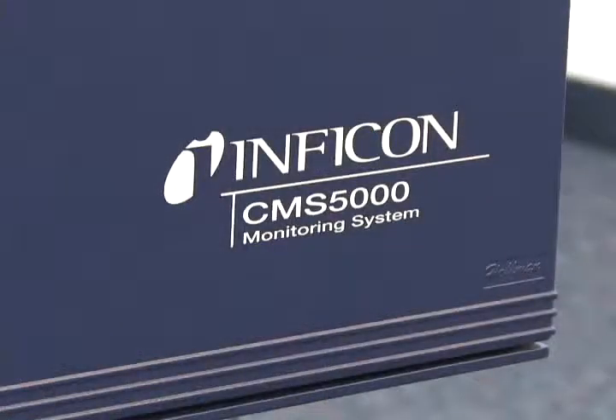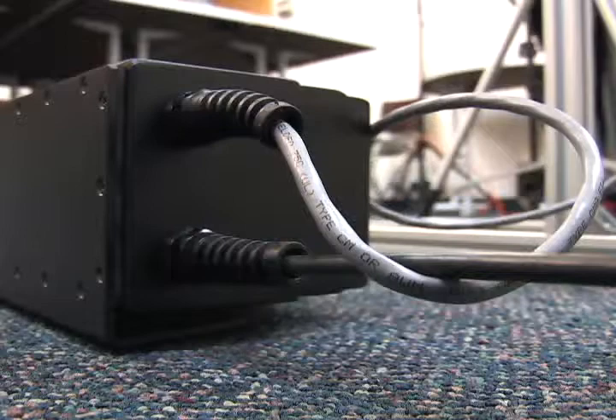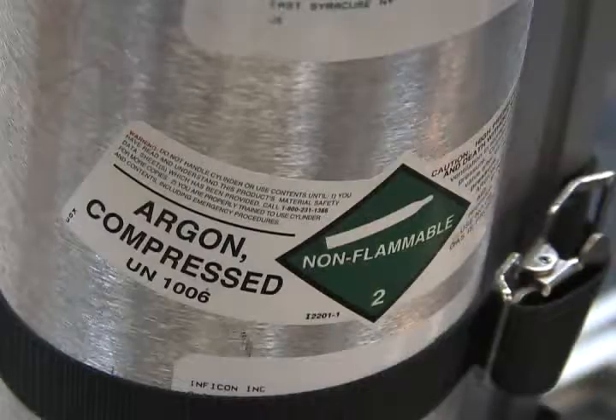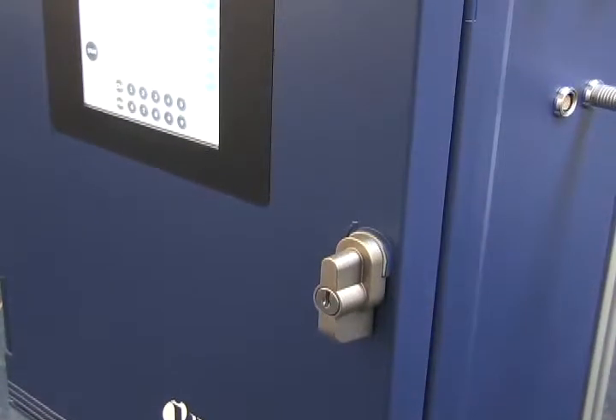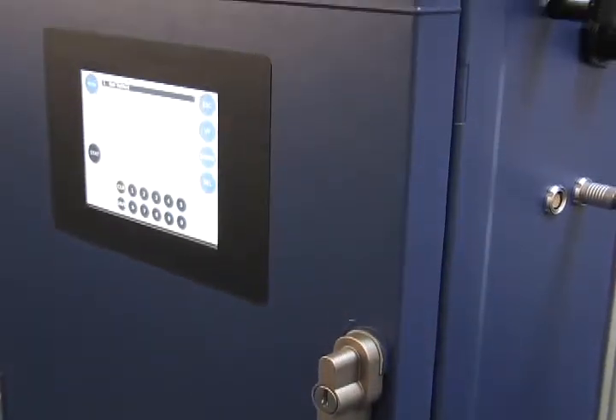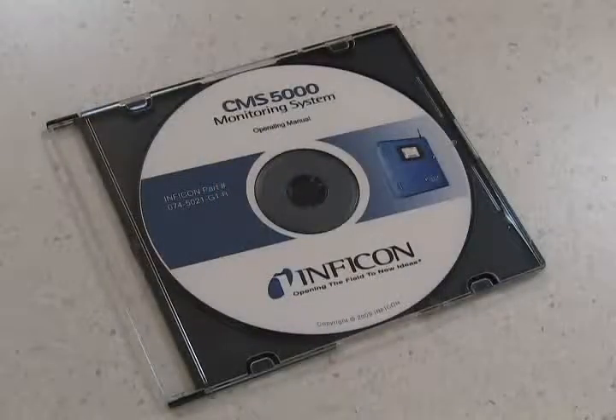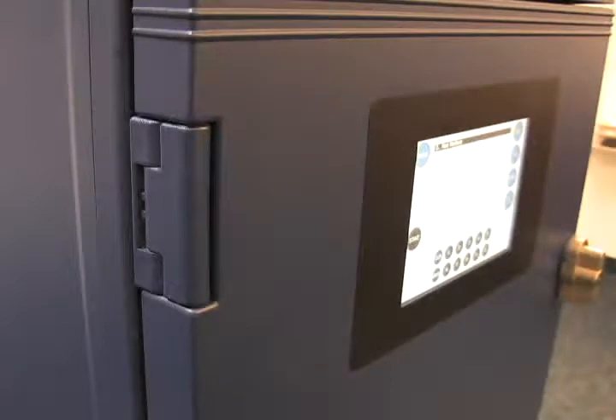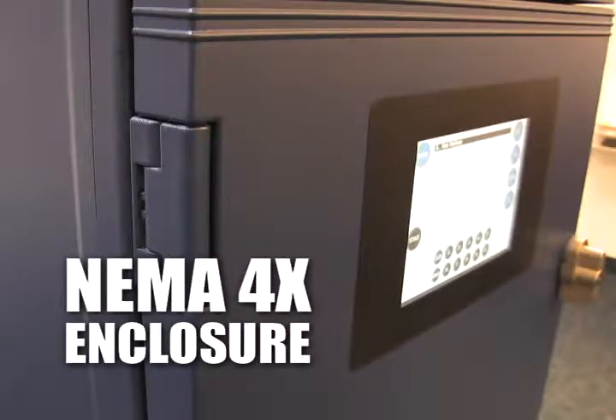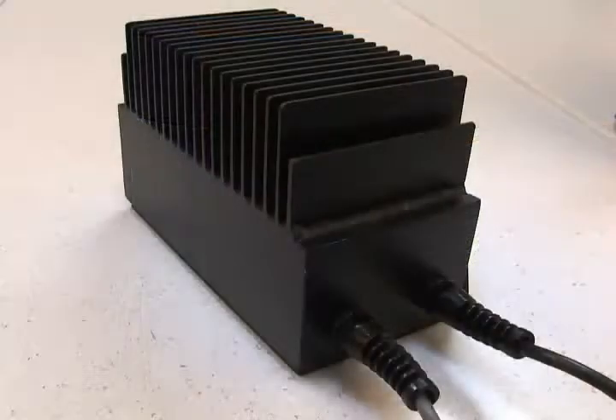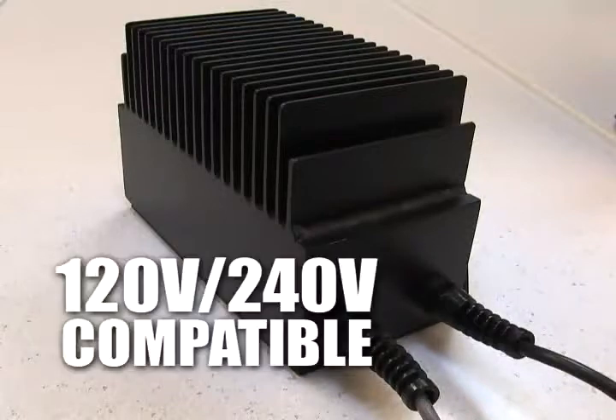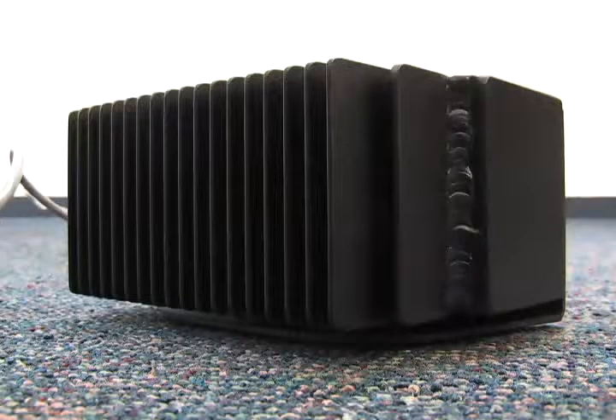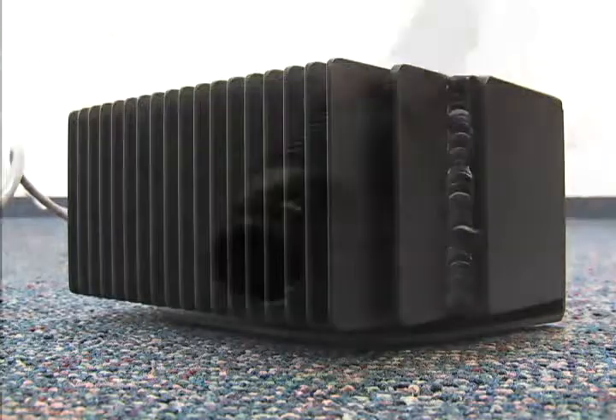The CMS5000 must have shore power available, as well as ultra-high purity argon for the carrier gas. The instrument is easily installed and simple to operate. A CD accompanies the instrument for easy training. The CMS5000 is housed in a waterproof NEMA 4X enclosure, making it suitable for outdoor use. The CMS5000 is 120 volts, 240 volts compatible. It uses a weatherproof AC-DC converter with a built-in surge protector.